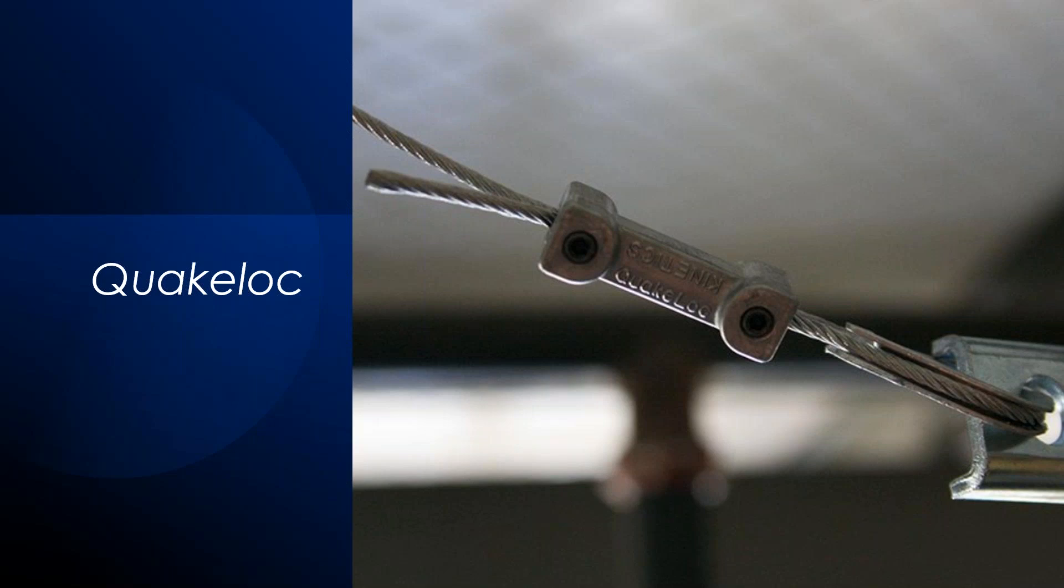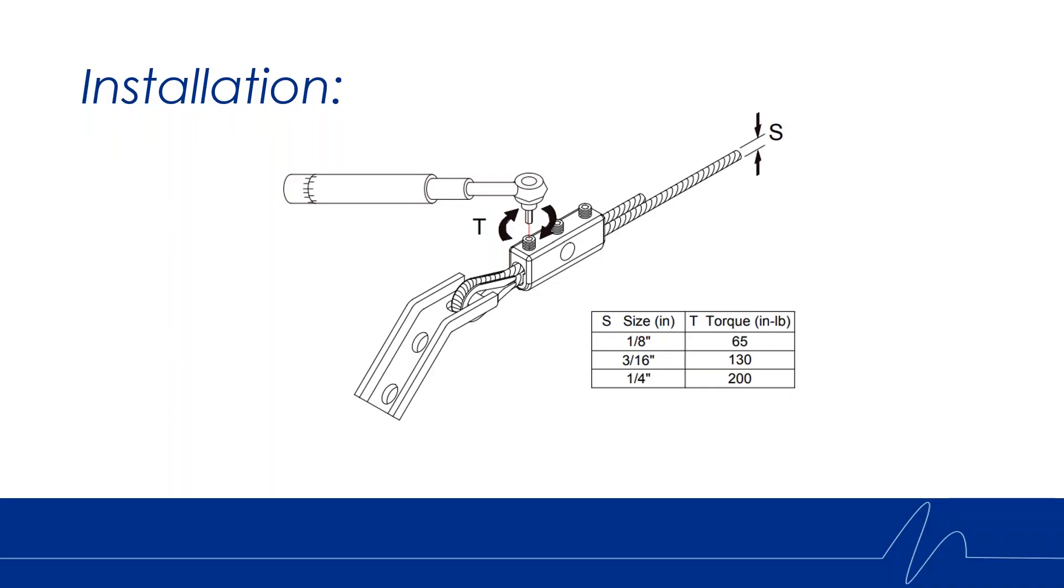However, the installation of the Quakeloc itself in the field can be sometimes a little lengthy and a little challenging. So in order to properly install a Quakeloc device, you do have to feed the cable through the Quakeloc twice. And then each one of the little adjustment screws does have to be torqued down to a certain torque setting using a torque wrench.